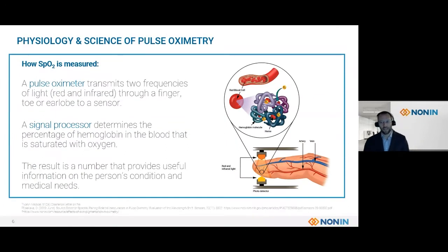So the science of pulse oximetry is really about the interaction of hemoglobin and red blood cells as it interacts with different colored lights. The summary of this is the image to the right, but I'll explain this a little further. These two different light sources are composed of red light, which we can see, and infrared light, which we can't. These two different light sources pass through the blood, pass through the body and go to the photodetector. The photodetector is where we are receiving the information from the light sources, and that's how we use an algorithm that's specifically developed for our pulse oximetry, and that's what calculates our SpO2 measurement. The result of this is a number that provides useful information to the patient's medical condition.